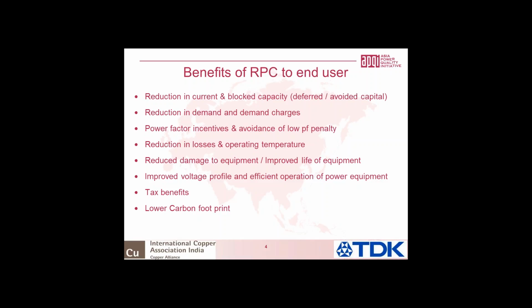When the currents come down, which is the first effect, there will be a reduction in losses, which means operating temperatures come down. Not only in India, in quite a few countries, it's been documented that one of the main reasons for distribution transformer failure is overloading, leading to excess heat of the oil paper insulation and eventual failure of the transformer. Such cases can be avoided. You have reduced damage to equipment and improved life of equipment.